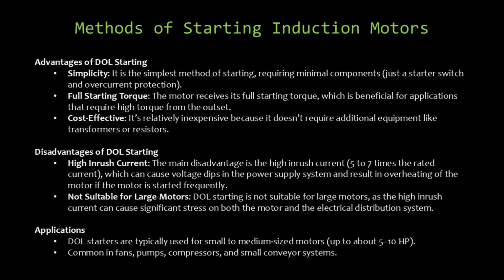Direct online starting offers several compelling advantages. Its simplicity is unmatched, requiring minimal components like a starter switch and overcurrent protection. The method provides full starting torque, which is crucial for applications demanding immediate power. Cost-effectiveness is another key benefit, as it doesn't require additional equipment like transformers or resistors. It's a straightforward solution for many motor starting scenarios.